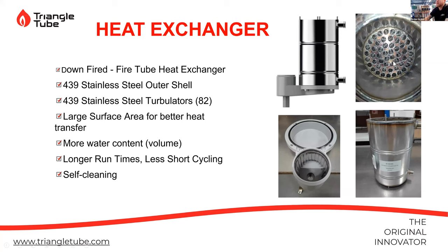All right, so I don't want you guys to think that this is self-cleaning for the life of the unit and you never have to pull it. 100%, you've got to pull it, and we'll go over some of the cleaning methods here in a little bit. So 439 stainless steel, large surface area in there. We've got a pretty good size heat exchanger. On the 110, the boiler holds about 2.5 gallons of water. The 155, about 3.5 gallons. And the 199, about 4.5 gallons.